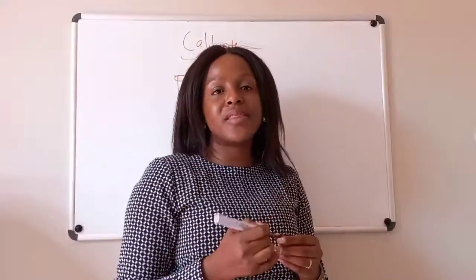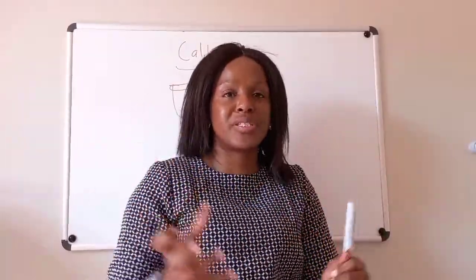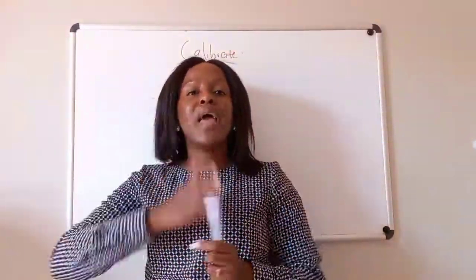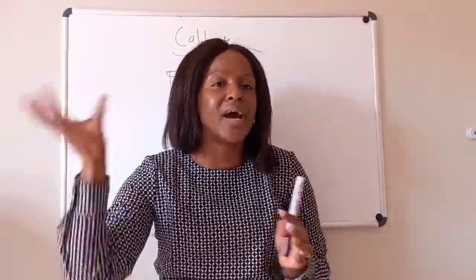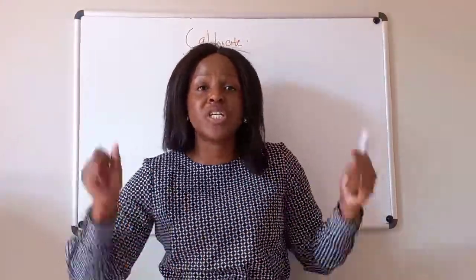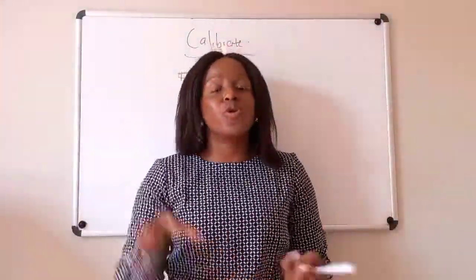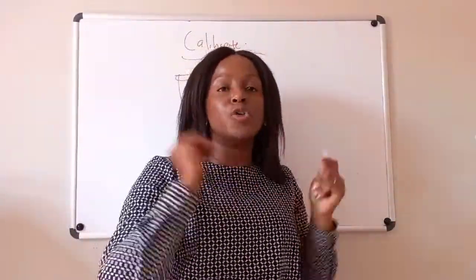Or you might find that with other instruments or other analytes, you get, let's say, 5 bottles of calibrators. All those bottles will have their known concentration, as well as their values depending on what method that instrument uses, if it's absorption, if it's light. So it will have the known values, and the instrument will just run them and plot a graph using those.